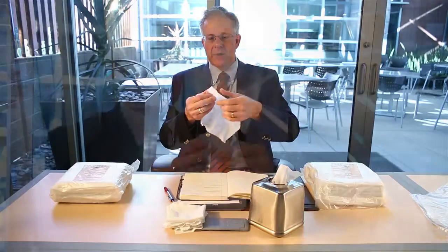So when someone says they're interested in a low lint wiper, the definition of a low lint wiper is a wiper that has particles that are 100 microns or larger. So a Kleenex could be a low lint wiper, right? 100 micron particles. I can see some particles coming off the edge of this wiper. Clearly they're visible to my naked eye. So a little bit of a misnomer, a low lint wiper, that's not a specification for a clean room wiper. That's a specification for an industrial rag. So let's cross that off. There isn't any such thing as a low lint wiper in a critical environment.